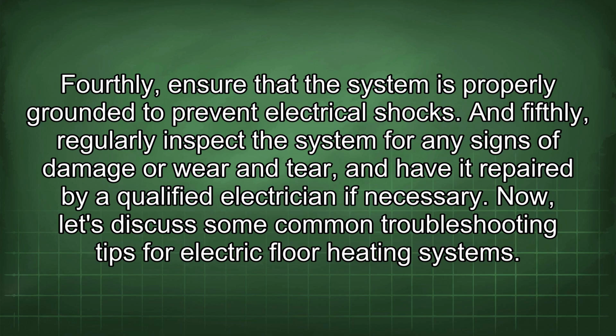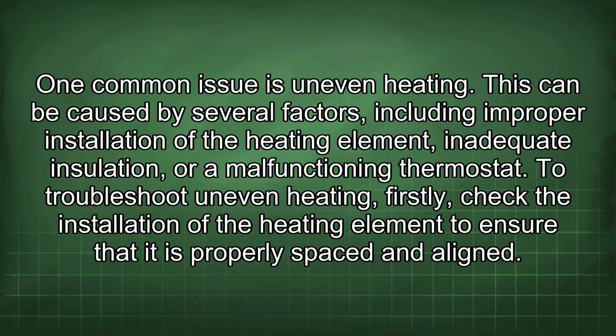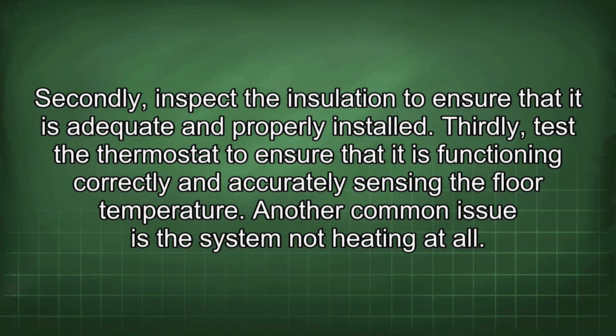Now let's discuss some common troubleshooting tips for electric floor heating systems. One common issue is uneven heating. This can be caused by several factors, including improper installation of the heating element, inadequate insulation, or a malfunctioning thermostat. To troubleshoot uneven heating, firstly check the installation of the heating element to ensure that it is properly spaced and aligned. Secondly, inspect the insulation to ensure that it is adequate and properly installed. Thirdly, test the thermostat to ensure that it is functioning correctly and accurately sensing the floor temperature.